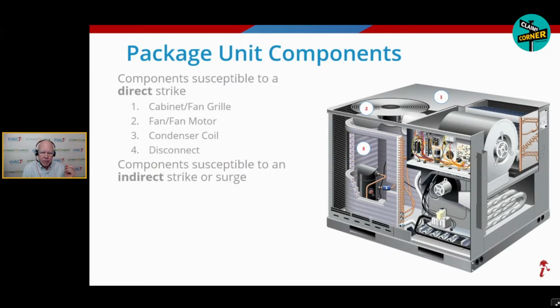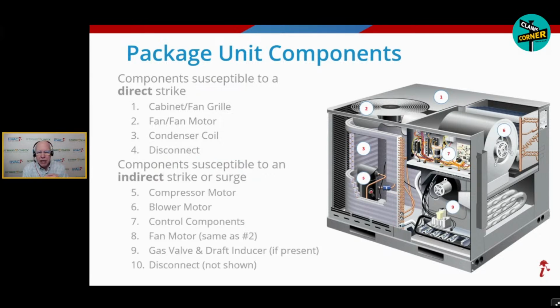Now, what are all those things that have wires in them? All the same things we just talked about, right? The compressor, the blower, the fan. If it's a furnace, not all package units are furnaces. When it is, a lot of times they call that a gas pack because it's working off natural gas. You could have a gas valve and draft inducer. In this picture, the disconnect's not shown. Something else a package unit could be that you don't think about all the time is a heat pump, right? So you wouldn't have all this gas and heat exchangers and burners in there. It would be a heat pump. You'd have reversing valves and some other stuff in there, maybe some heat strips, electric heat strips, and things like that. So don't forget these package units could also be heat pumps, or they could just be straight cool and used for air conditioning only.